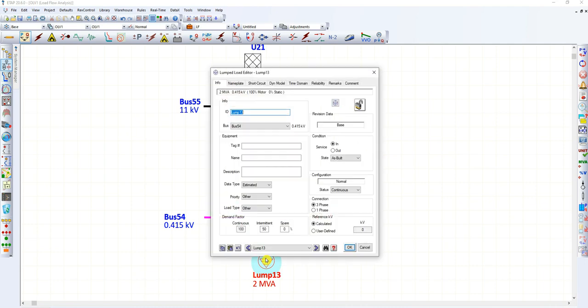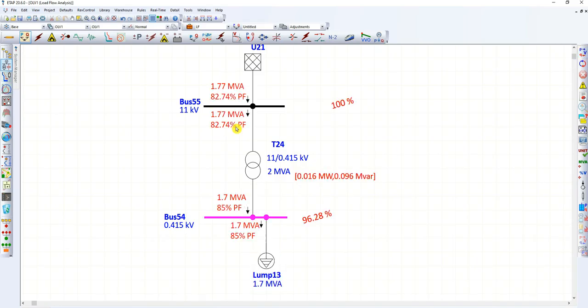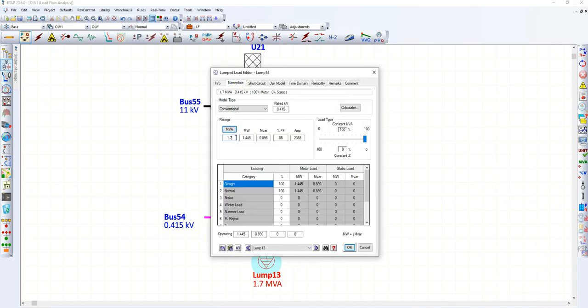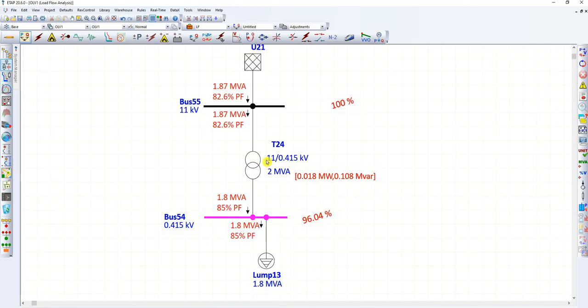Now let's adjust this load. Instead of 2 MVA, let's consider 1.7 MVA. It is now drawing 1.77 MVA, and since the transformer rating is 2 MVA, the transformer is not overloaded — previously it was shown in red, meaning it was overloaded. We can load more than 1.7 MVA; let's try 1.8 MVA. It is drawing 1.87 MVA — let's increase further.